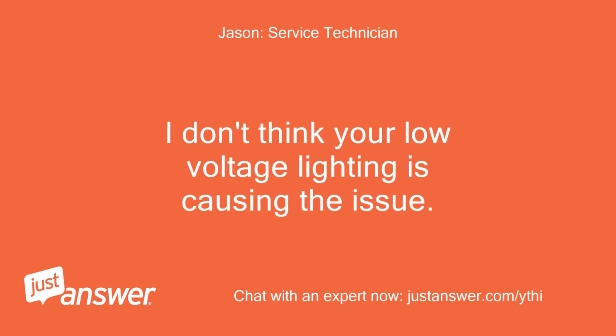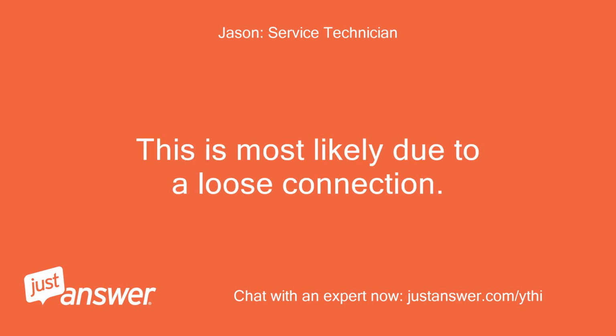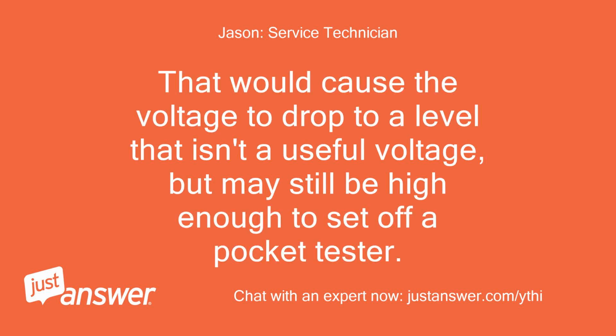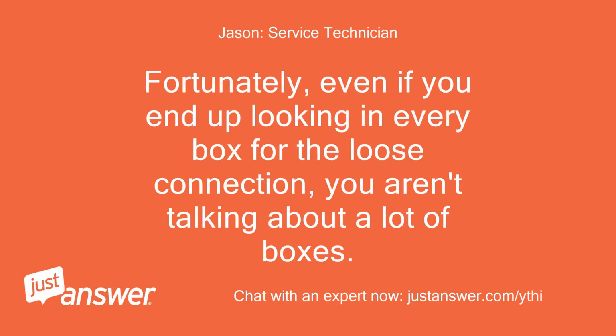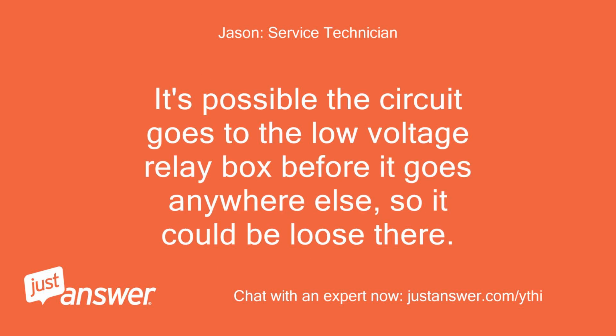I don't think your low voltage lighting is causing the issue. This is most likely due to a loose connection. That would cause the voltage to drop to a level that isn't a useful voltage, but may still be high enough to set off a pocket tester. Fortunately, even if you end up looking in every box for the loose connection, you aren't talking about a lot of boxes. It's possible the circuit goes to the low voltage relay box before it goes anywhere else, so it could be loose there.